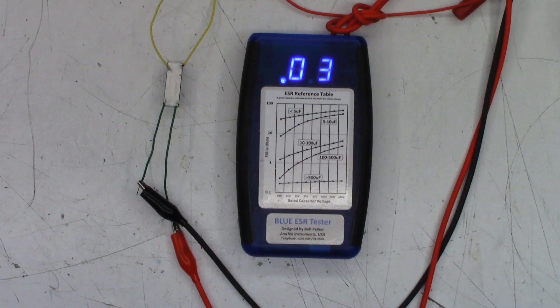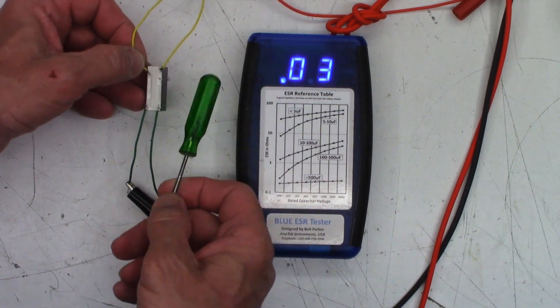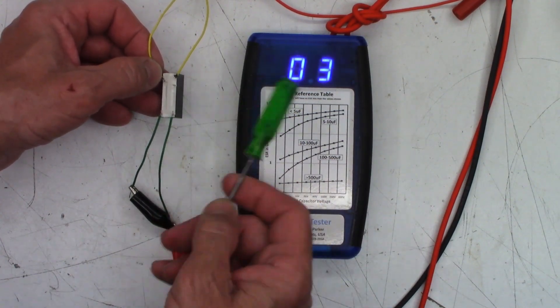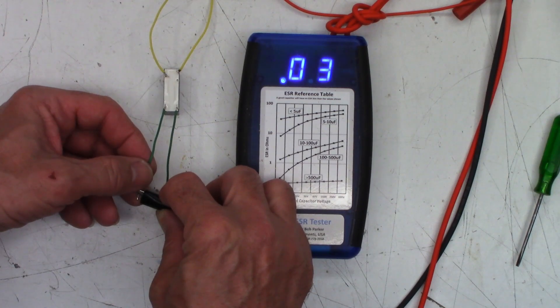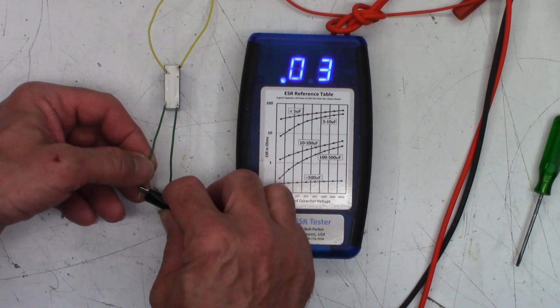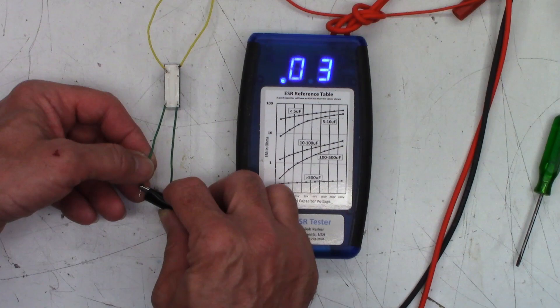Let's go ahead and give it some constant voltage, and then we'll give the relay a little tap. It's staying perfectly sound — interesting. We were staying between 0.02 and 0.04 ohms. That is very interesting that it is working perfectly now.